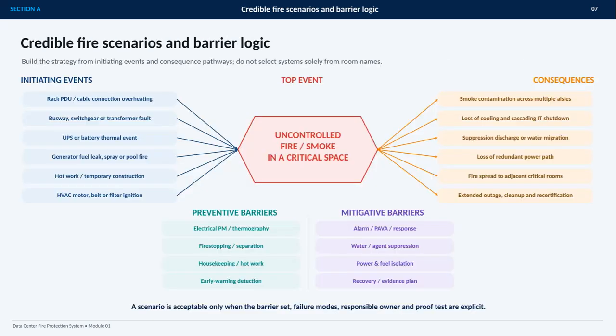This section frames fire protection around credible scenarios, rather than relying on room names alone. I start with the initiating events. Overheating at a rack PDU or cable connection, faults in busways, switchgear, or transformers, a UPS or battery thermal event, generator fuel release, hot work, and ignition involving HVAC equipment. These are the conditions that can begin the event.